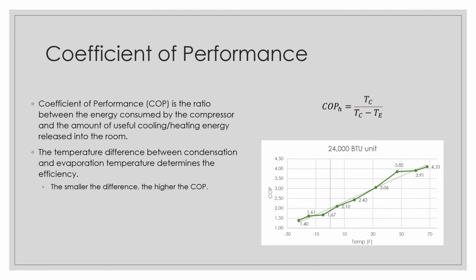Theoretical COP values can be found by calculating the difference between the condensation and evaporation temperatures at different outdoor temperatures, using the equation to the right. As you can see in the graph, the smaller the temperature difference is, the higher the COP is, and the higher the COP is, the lower the cost to run the heat pump is. Using weather data for the desired location and the provided COP values of our heat pump, an annual cost to operate the heat pump can be calculated.